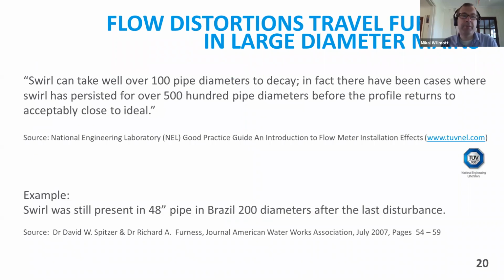The National Engineering Laboratory, which is a really good lab based just outside Glasgow in Scotland, has written that swirl can take over 100 pipe diameters to decay. Now, swirl is probably one of the worst distortions you can find. It goes on. In fact, there have been cases where swirl has persisted for over 500 pipe diameters before the profile returns to acceptably close to ideal.